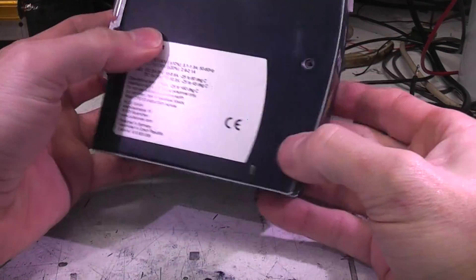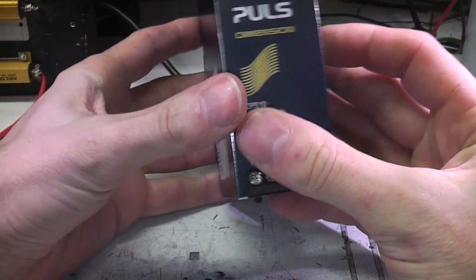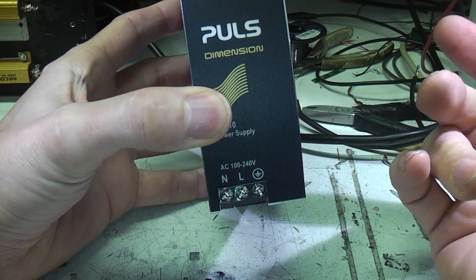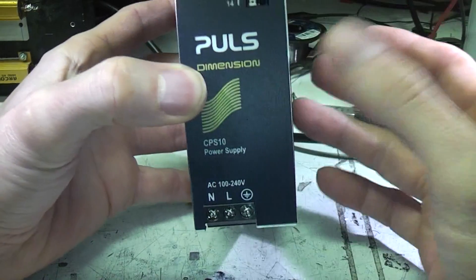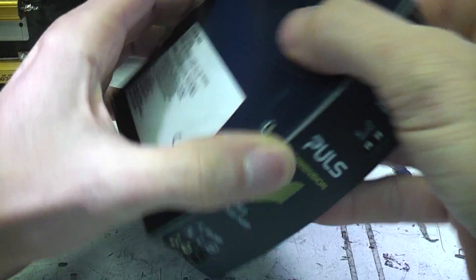A while ago I looked at a PULS DIN rail power supply. PULS are a fairly high-end manufacturer of DIN rail industrial power supplies. They sent me this one to have a look at — this is a new one, the CPS 10 range. It has a couple of unusual features. One is it's pretty small — this is a 24 volt 10 amp power supply, so 240 watts nominal, and it's pretty small for that sort of power range.